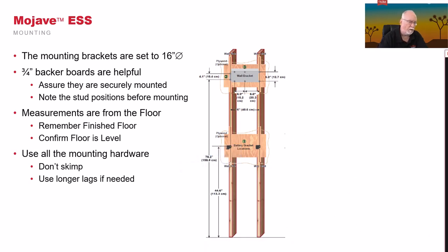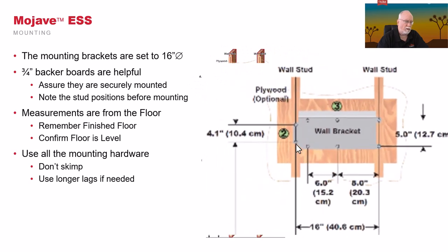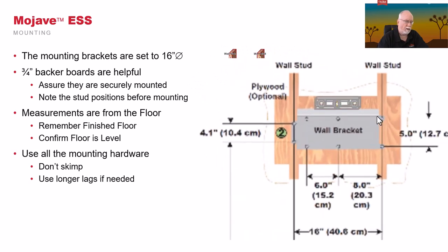So the first thing you're going to do is mount that. Then you're going to go 44.6 inches. You're going to put in the bolts for the ESS. Again, these will be lined up directly on the studs. And then finally, when you put the unit up on the wall, go ahead and use a level, make sure that it's level, and then put in the second wall studs. Now, important things, studs have to be 16 inches on center. I would suggest you use longer bolts than what we provide for doing this particular part of the install.